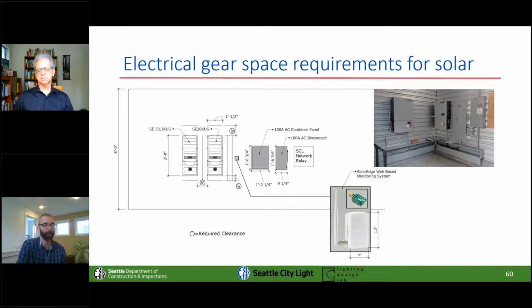On energy code projects, we see anywhere from 1 to 3 different inverters used. Then you have some additional equipment, where we need to combine the output of multiple inverters or multiple streams of microinverters into a single circuit. We'll use essentially a sub panel, but it's dedicated for combining solar outputs, as well as a disconnect. And if you're in the downtown ring network, the utility is going to require a network relay to make sure the solar does not backfeed into the ring network and create equipment issues. That can be an additional cost as well.